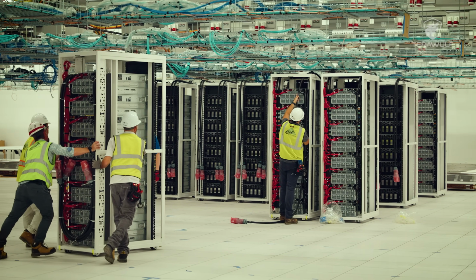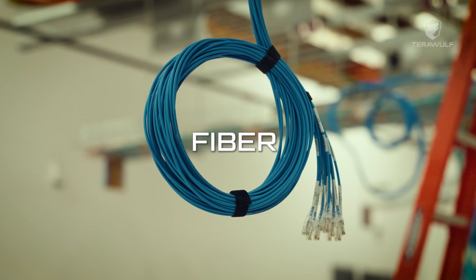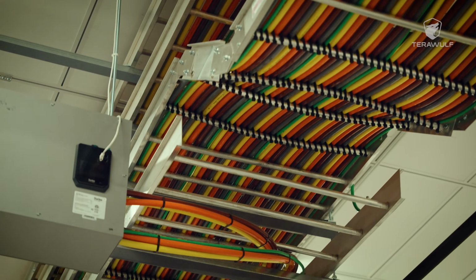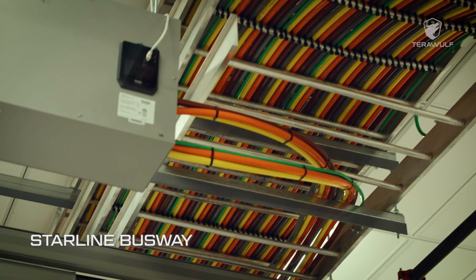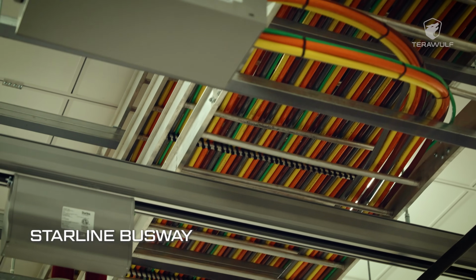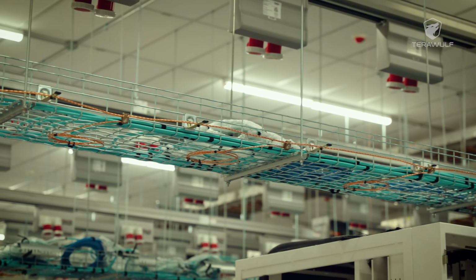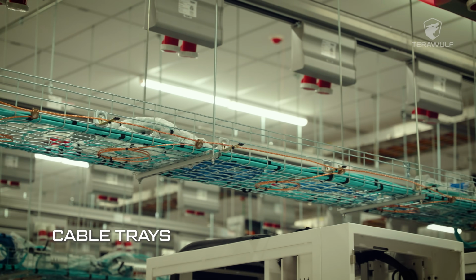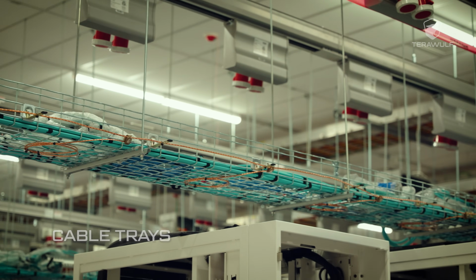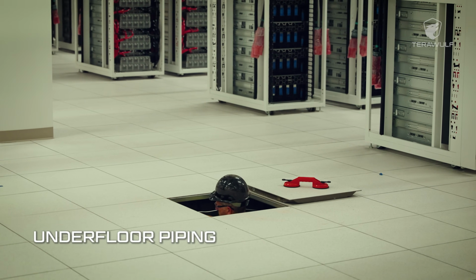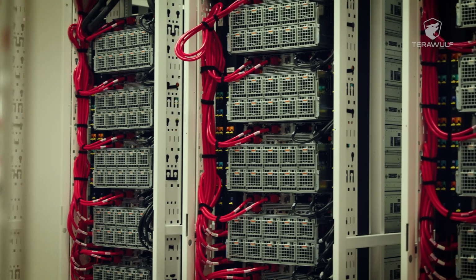So this is the data hall, the heart of the operation, with three primary parameters: power, fiber, and underfloor piping. Overhead, we've implemented a Starline busway system to deliver modular, high-capacity power distribution. Next, you'll see our cable trays, which separate data and power cabling to reduce electromagnetic interference. Under the 36-inch raised floor is the mechanical piping with varying configurations of direct liquid-to-chip and rear door heat exchangers for liquid supply.